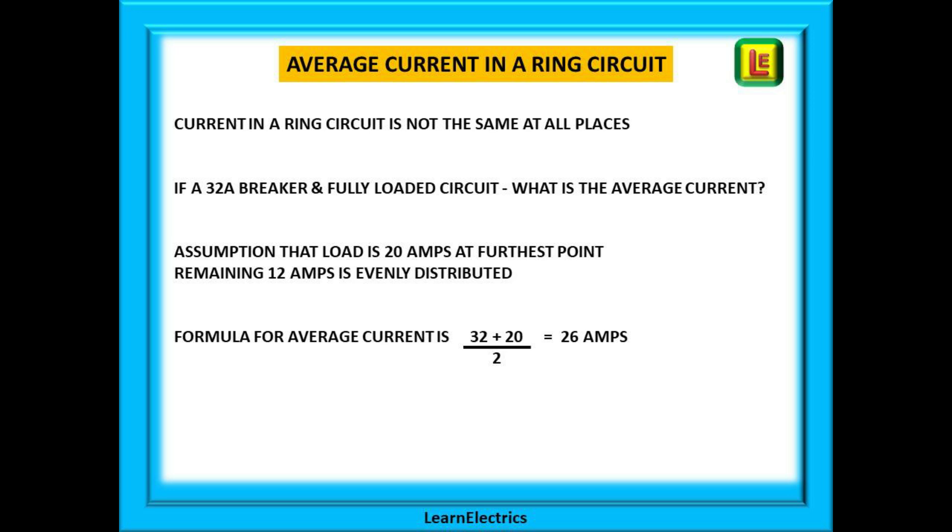If we have a fully loaded 32 amp circuit, what then is the average current? We made an assumption earlier that the furthest point of use, the midpoint, would have a 20 amp demand and that the remaining current is evenly distributed. We can use a little formula now.